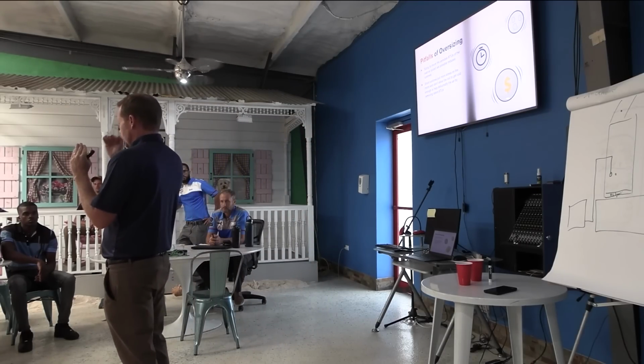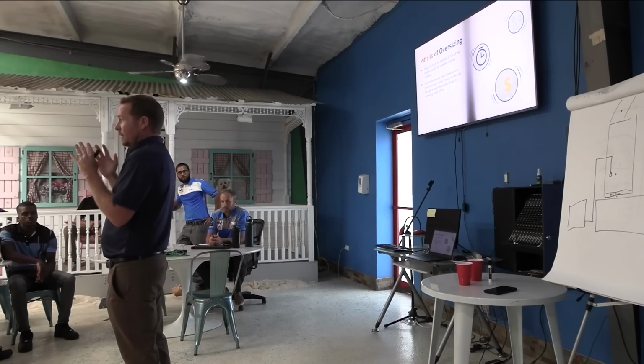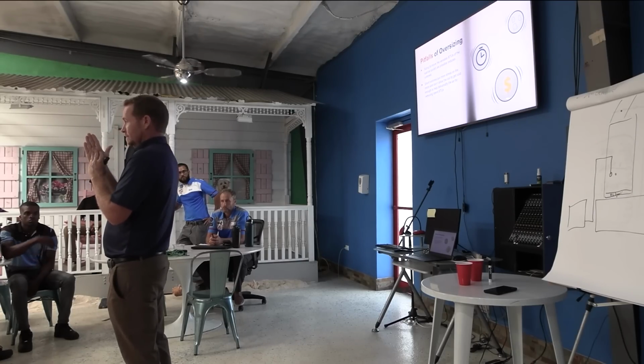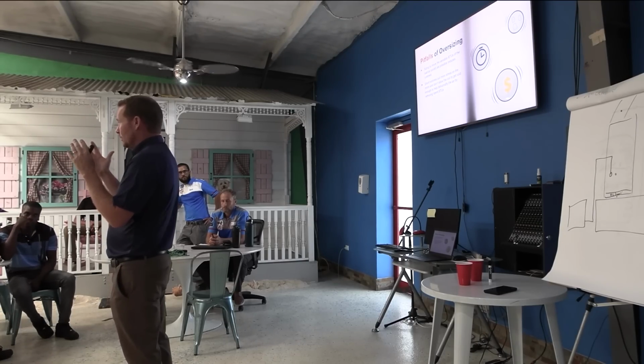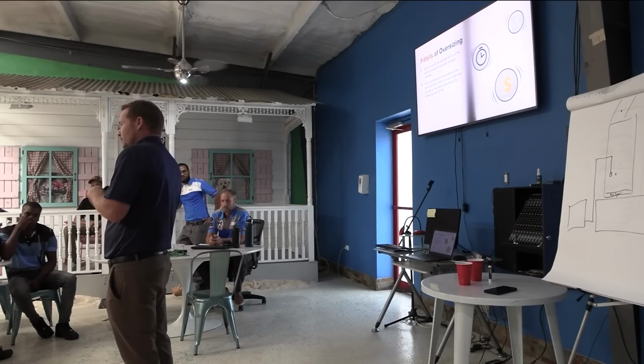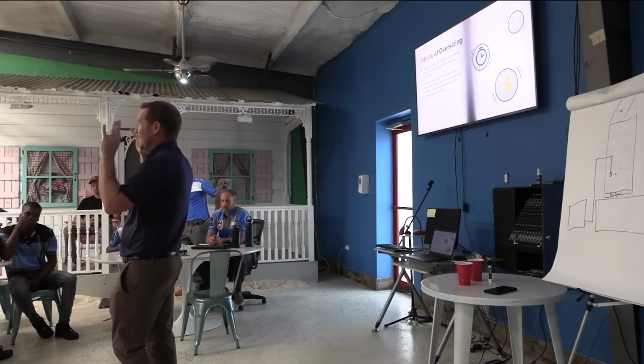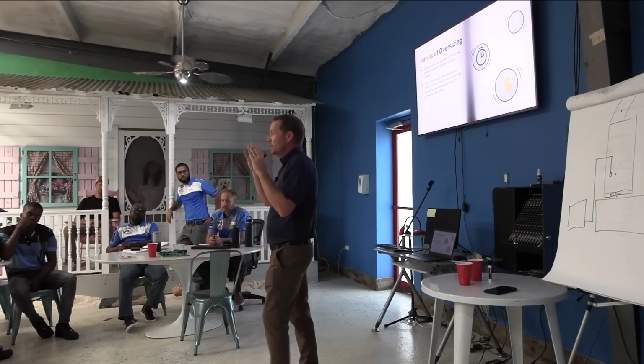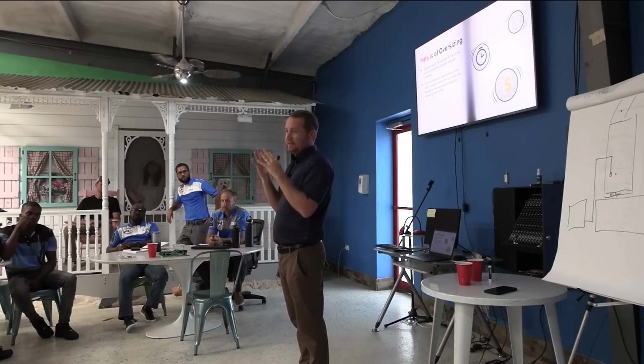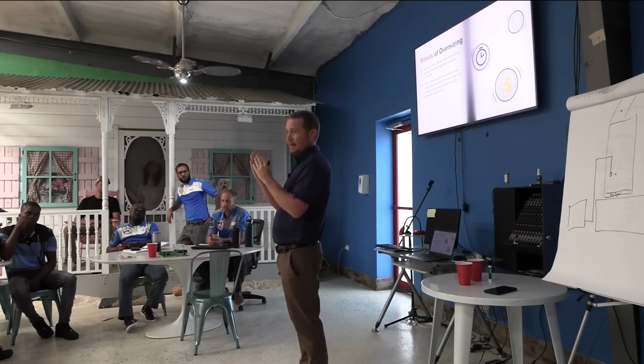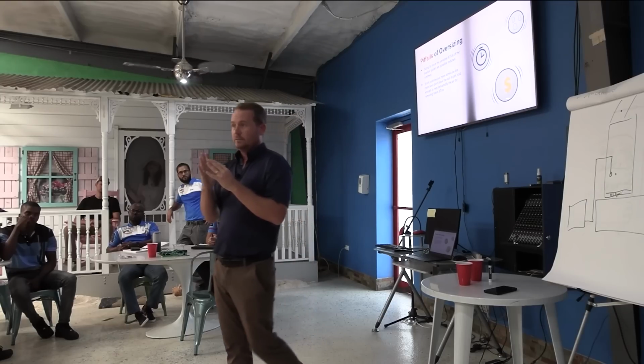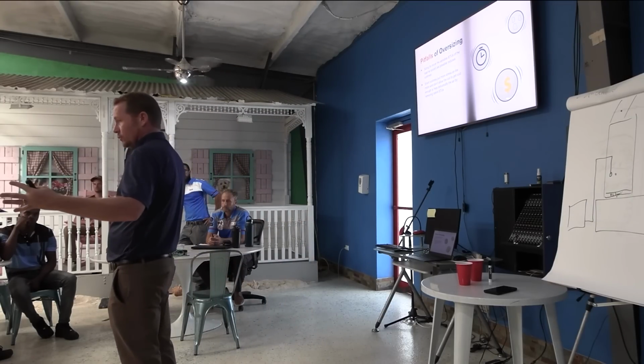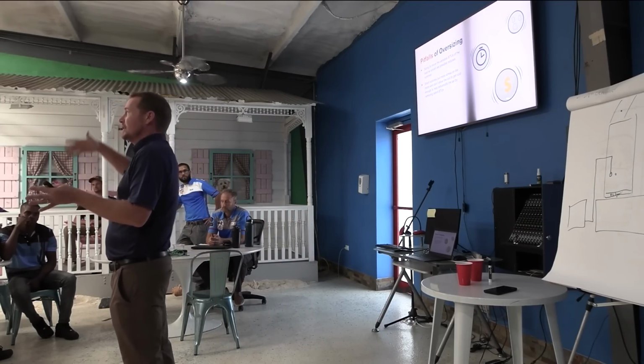And so you get what's called a higher bypass factor. When you have a faster face velocity over an evaporator coil, less of that air is actually dwelling on the surface of the coil. The coil temperature may be the same and the air moving the same speed, I mean the math probably doesn't work out exactly right, but you're not going to get the dehumidification you're looking for because the dwell time on the coil isn't as long. You want the air to be moving. A larger coil is not a bad thing, just get your airflow right.